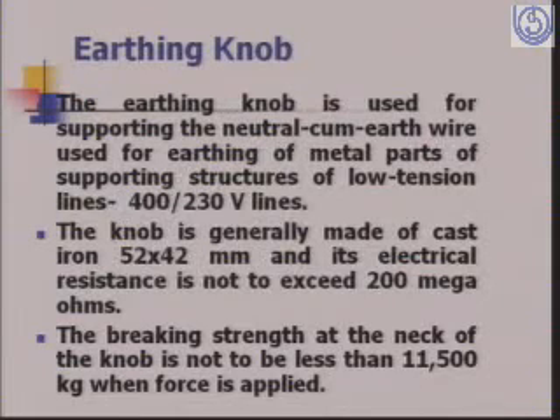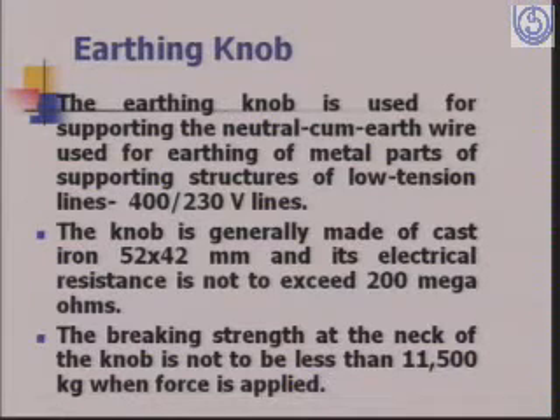Then we have the earthing knob. The earthing knob is used for supporting the neutral cum earth wire used for earthing of metal parts of supporting structures of low tension lines. The knob is generally made of cast iron and 52 into 42 mm, and its electrical resistance is not to exceed 200 mega ohms. The breaking strength at the neck of the knob is not to be less than 11,500 kg when force is applied.